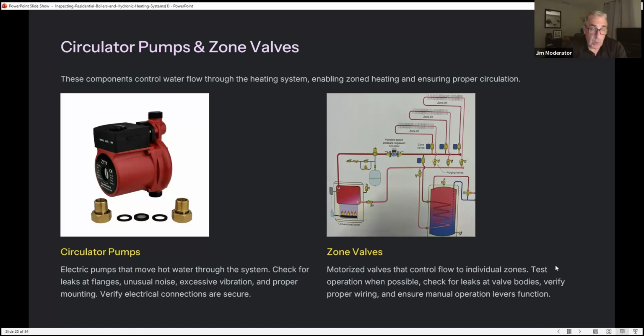So the older systems, you're going to know. I've run into systems where they're 40 years old and they look like they just came out of the showroom, like a car. You have somebody there that cleaned that unit every week. And if you were a layman just walking by, you'd say, man, that's a real nice heating system. But then I'll look at the circulator and it's the size of a football. So it's an older system. So take a look at your circulators. Again, you're really checking for leaking, rust, and operation. You'll hear them when they're running.